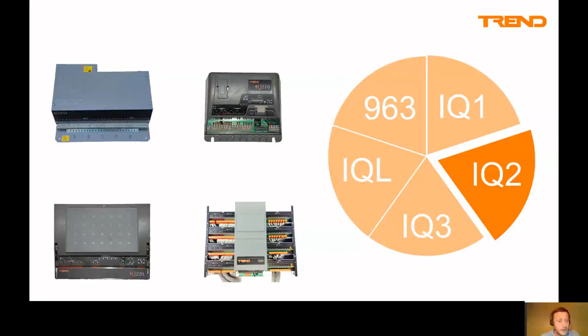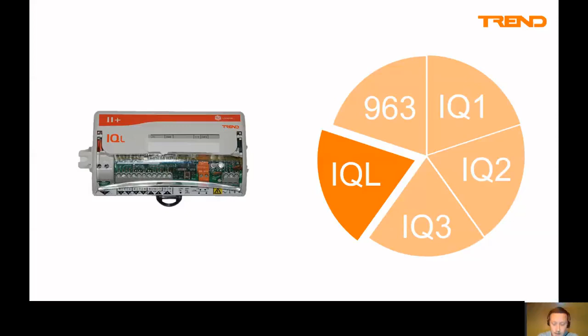As a note of caution on the IQL, the L bit stands for LON, a protocol that the IQL communicated across. We do still find these out in the field. If an IQL had failed in a fan coil unit, for example, there is no direct replacement from the trend perspective with LON, so you'd have to replace it with a BACnet-based controller. There's no way we can put a BACnet controller directly on a LON network. So while the obsolete comment I made earlier about backward compatibility is relevant in some instances, in others it's not, and you're forced into an upgrade as things fall off. An IQL is LON, and you should definitely be thinking about replacing it.